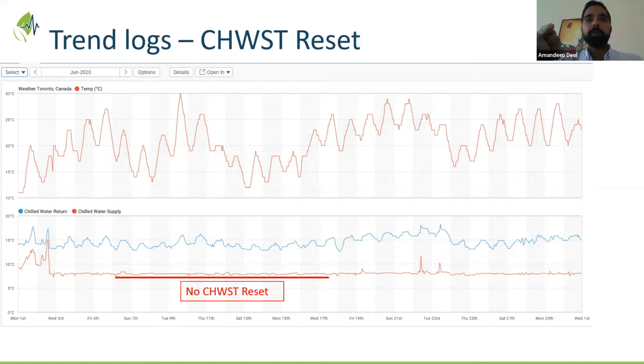And at the bottom graph, you see two lines, blue and red. Red is the supply water temperature, and blue is the return water temperature from the chiller plant. So what you could see in this graph is that even with the temperature dropping in the middle of June, almost close to 15 or even close to 12 degrees C, currently there's no reset on the chilled water supply temperature. No automatic reset. Rob's no automatic, yes. Manually. Okay. Yes, they do it manually.